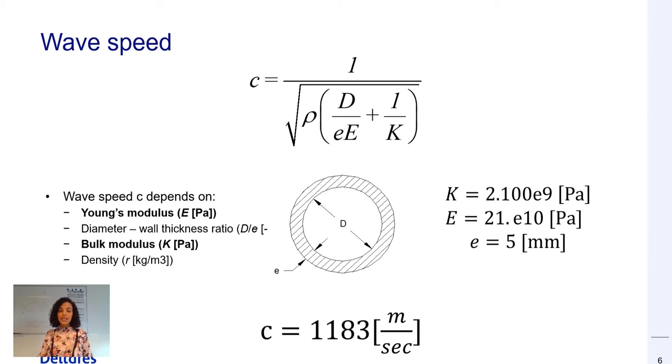In our case, the liquid is water. The bulk modulus value for water is automatically updated in Wanda in the fluid window. And we assume the following values for our Young's modulus and wall thickness. By conducting the calculation, we get a wave speed of 1,183 meters per second.